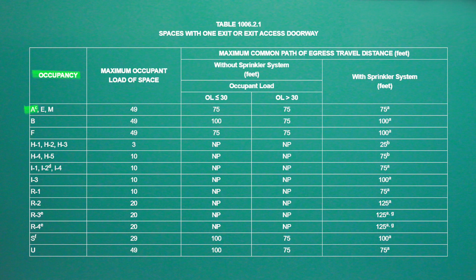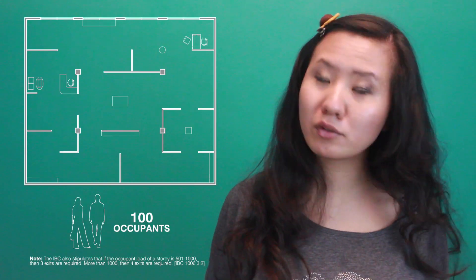which indicates that if the space only has one means of egress, the occupant load cannot exceed 49. In our case of 100 occupants, we would have to provide two means of egress.